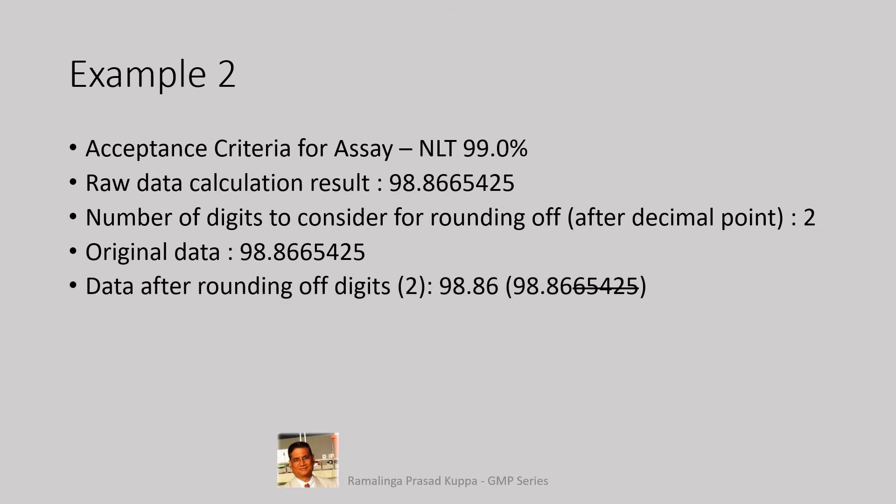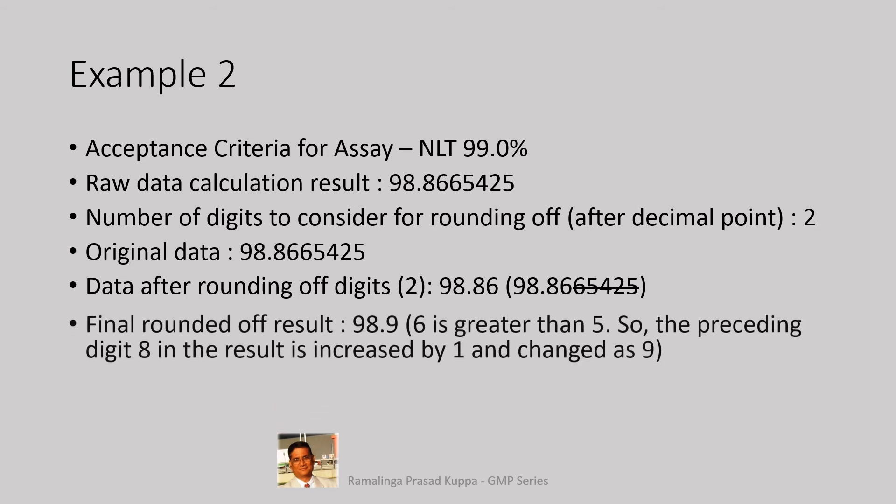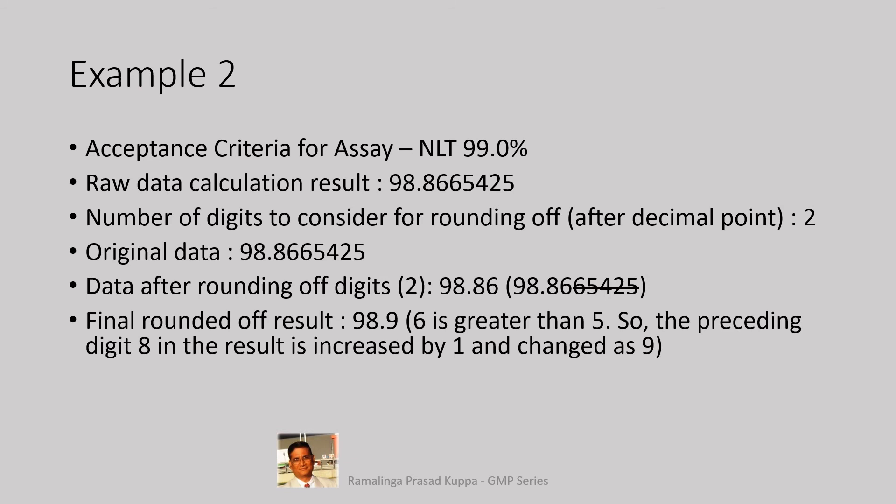Data after rounding off to 2 digits is 98.86. Data after ignoring the last 5 digits, the result is 98.86 for rounding off. Final rounded off result is 98.9. 6 is greater than 5, so the preceding digit 8 in the result is increased by 1 and changed as 9. The last digit in the result is 6, which is greater than 5. So, the preceding number 8 is rounded off to 98.9%. Reported result of assay was 98.9%. Decision fail. This is a failure value.